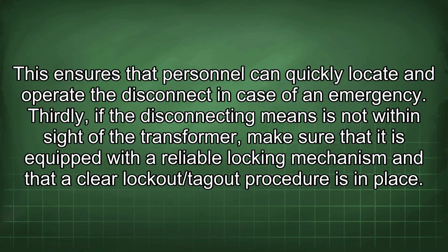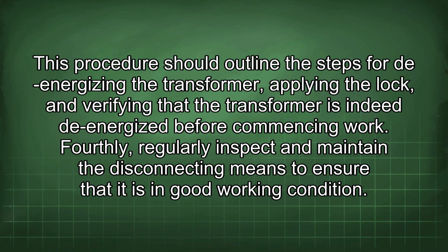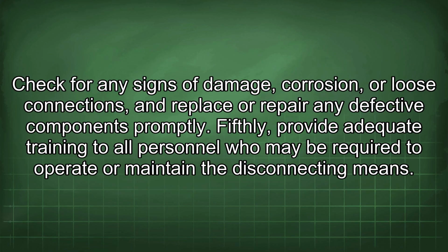Thirdly, if the disconnecting means is not within sight of the transformer, make sure that it is equipped with a reliable locking mechanism and that a clear lockout/tagout procedure is in place. This procedure should outline the steps for de-energizing the transformer, applying the lock, and verifying that the transformer is indeed de-energized before commencing work. Fourthly, regularly inspect and maintain the disconnecting means to ensure that it is in good working condition. Check for any signs of damage, corrosion, or loose connections, and replace or repair any defective components promptly.